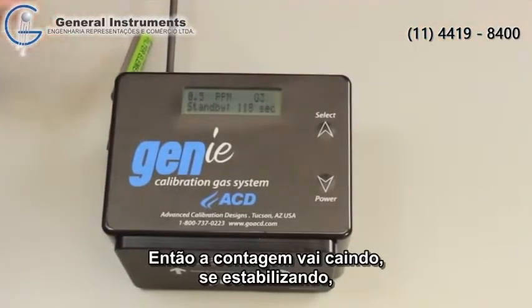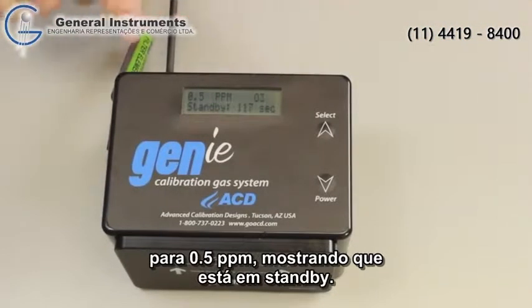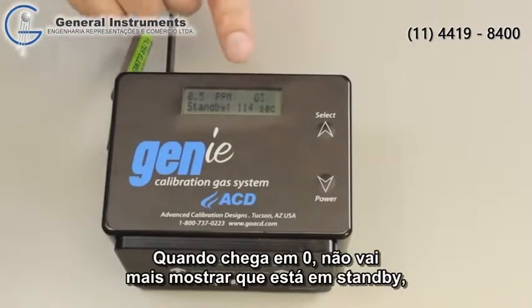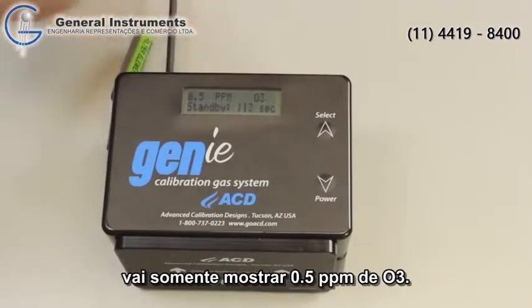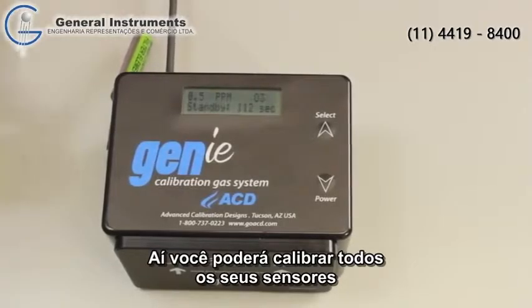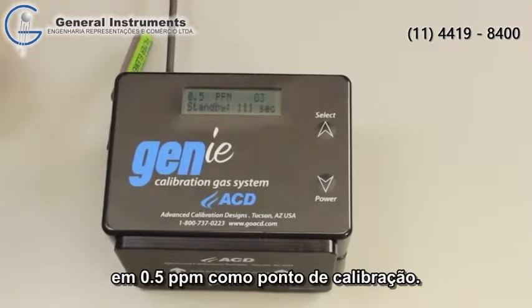So as it comes down, it says stabilizing 0.5 ppm, standby. So standby 150. When it counts down to 0, it will no longer say standby. It'll just say 0.5 ppm ozone. All right. So now you can calibrate all your sensors that have 0.5 ppm as their calibration point.